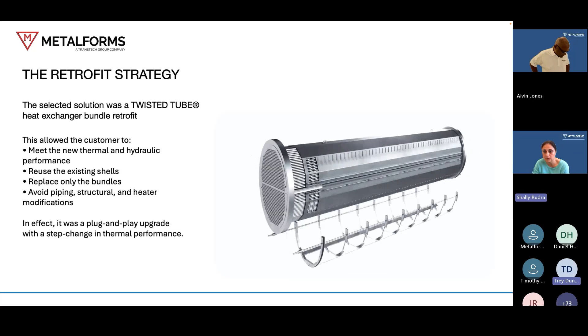Again, key considerations why this solution worked: twisted tube technology essentially works on the three parameters that affect the duty of a heat exchanger. The first one being U value or heat transfer coefficient, the second one being surface area, and the third one being the log mean temperature difference, or the driving force for heat transfer. The shape of the tube after it's twisted leads to the elimination of traditional segmental baffles, and the tubes are placed on a triangular pitch. Due to the shape of the tube, we're able to fit a large number of tubes within the same shell because the tubes are placed on a pitch that is tighter than TEMA. So that's how it works on the A, or the area.